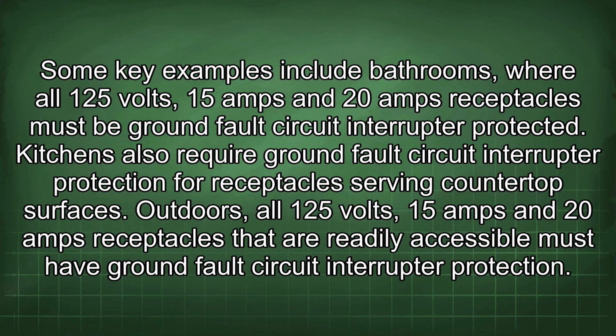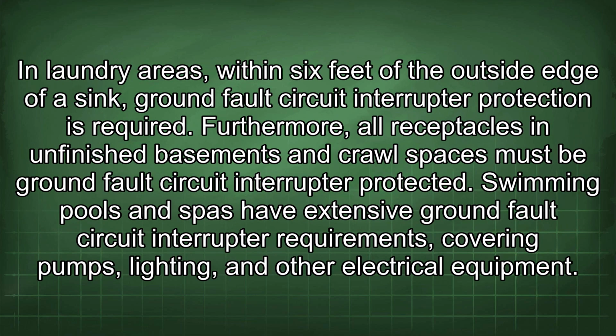Outdoors, all 125 volt, 15 amp and 20 amp receptacles that are readily accessible must have ground fault circuit interrupter protection. In laundry areas, within 6 feet of the outside edge of a sink, ground fault circuit interrupter protection is required. Furthermore, all receptacles in unfinished basements and crawl spaces must be ground fault circuit interrupter protected. Swimming pools and spas have extensive ground fault circuit interrupter requirements covering pumps, lighting, and other electrical equipment.